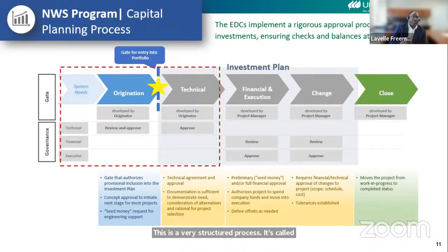It's called the Eversource Capital Project Approval Process, probably the same name at UI, different teams, same functions, but it's designed to ensure that all considerations, whether environmental, policy, or technical, are considered, and also that other needs within the enterprise in the same area are considered, such that we don't touch a substation and upgrade it for capacity without addressing a pending obsolescence or asset condition need at the same substation, requiring us to go back several years later to touch the same substation. So if we have a project, it's imperative that we collect all the needs and co-optimize them such that we're doing the most cost-effective activities for customers in every location.